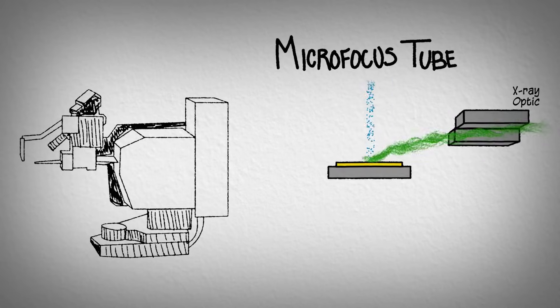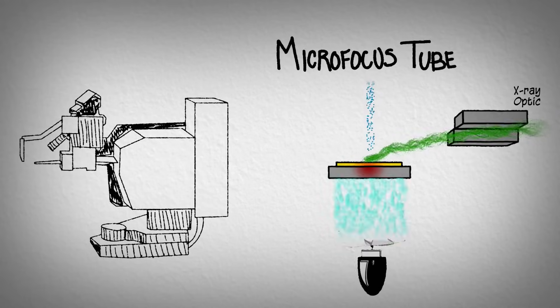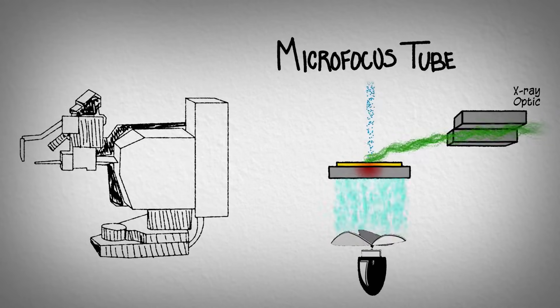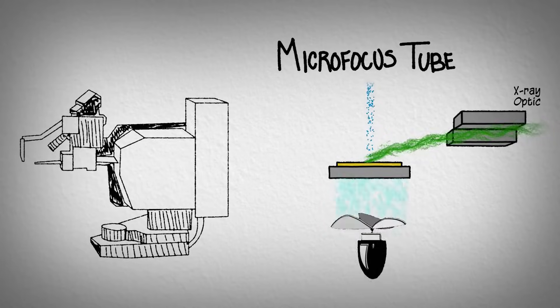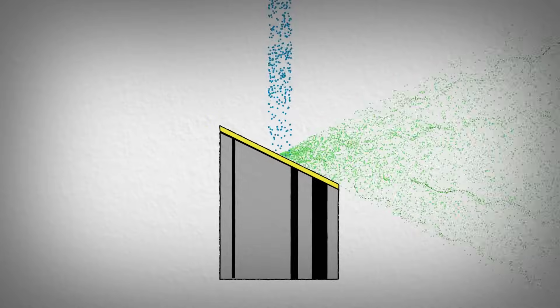By using a small, spot-shaped electron beam, heat can be dissipated in three dimensions. These microfocus sources allow the anode to be air-cooled and produce a very bright, point-focus beam. The source intensity can be further improved by optimizing the takeoff angle.